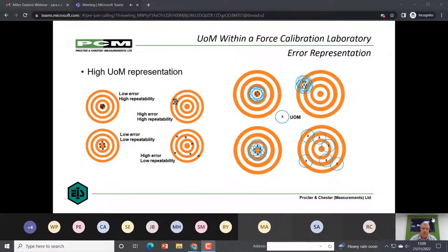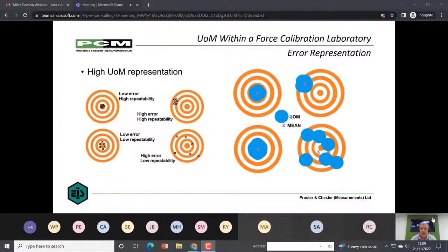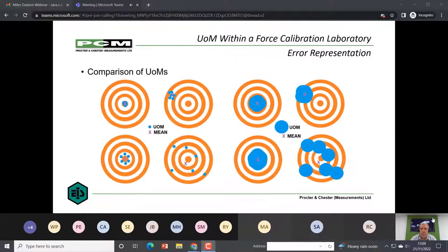So if you use the same representation for a facility that gives you a high uncertainty of measurement, the actual values don't change, but the uncertainty associated with those measurements does change. So here you can see the representation of where the uncertainty of that measurement series lies. If you put the mean on, the mean sits within those. And when you compare a facility that gives you a low uncertainty of measurement with a higher uncertainty of measurement, you see straight away that the means don't change. But what will change is the uncertainty associated with those measurements that you've just taken.